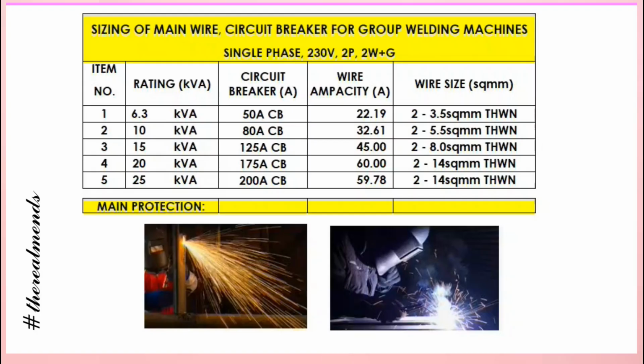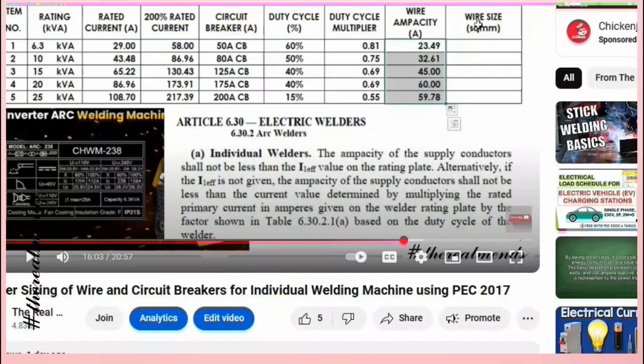This time we have another topic, which is the sizing of main wire and circuit breaker for a group of welding machines, that is single phase 230 volts, 2 pole, 2 wire plus ground. So this time, these are individual welding machines, as you can see. The sizing of the main wire and circuit breaker of an individual welding machine is content we already covered last time. You can check my YouTube account. Please check the sizing of wire for an individual welding machine using PEC 2017. Here is the detailed explanation of how we arrive at the circuit breaker and the wire ampacity.